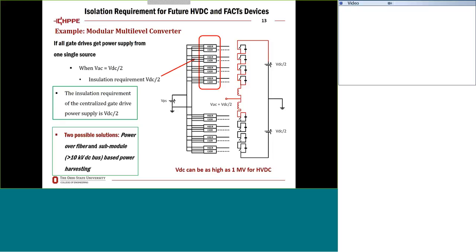So there are two possible solutions. One is power over fiber. The other is sub-module DC bus-based power harvesting, where we take power directly from the DC capacitor of each module. You might say the second method is already widely developed for existing applications, and yes, it is. But when we use higher voltage rated devices, the challenge is much greater, and we need to look at totally different approaches.